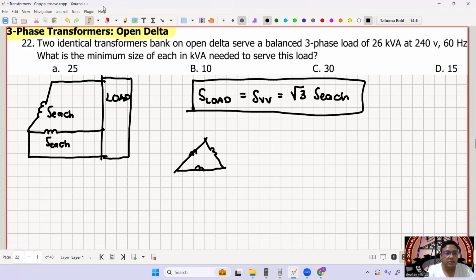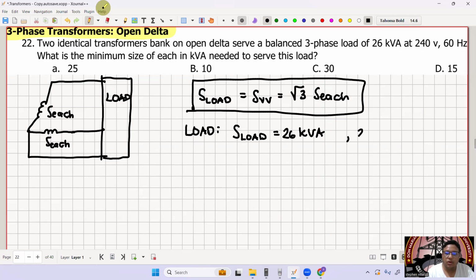Okay? So sige, let's try to solve number 22. Two identical transformer banks on open delta serve a three-phase load of 26 kVA. So ito yung load natin, no? So S load is equal to 26 kVA, and this is at 240 volts, 60 hertz. What is the minimum size of each in kVA needed to serve this load? So ano daw yung ating rating dapat ng ating transformer in open delta? So ang tinatanong is S each.